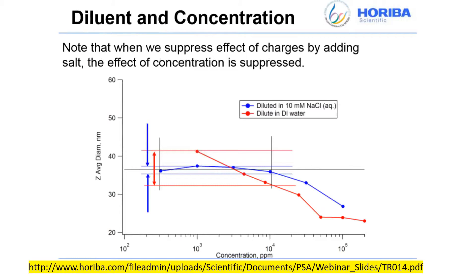The idea is to simply make measurements over a range of dilutions, typically a series of two-fold dilutions. You want to choose a dilution that puts you in the flat part of the response graph — ignore the red line since it is specific for particle sizing, not zeta potential measurement. You also want to pick a dilution that has the lowest variability for repeated measurements. In this case, the flat response spans more than one and a half decades.